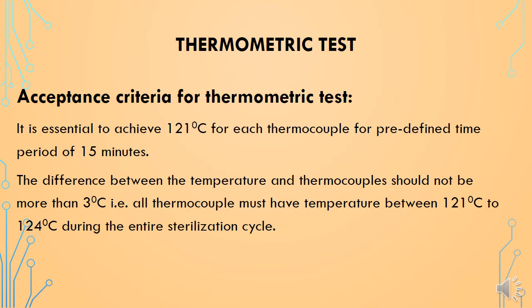Acceptance criteria for the thermometric test: it is essential to achieve 121 degrees Celsius for each thermocouple for a predefined time period of 15 minutes. The difference in temperature between thermocouples should not be more than 3 degrees Celsius — that is, all thermocouples must have temperatures between 121°C and 124°C during the entire sterilization cycle.